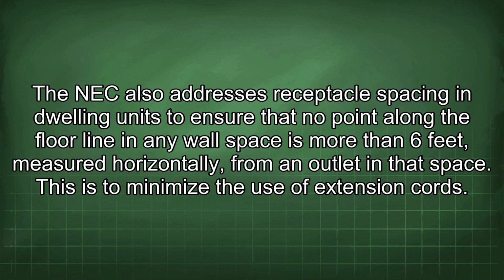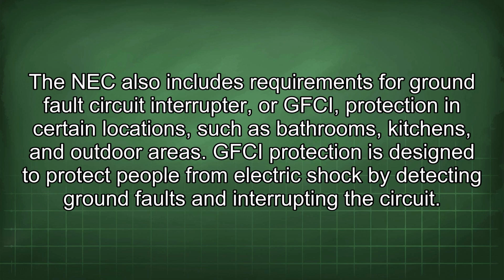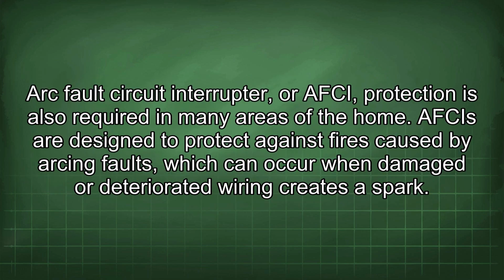The NEC also addresses receptacle spacing in dwelling units to ensure that no point along the floor line in any wall space is more than 6 feet, measured horizontally, from an outlet in that space. This is to minimize the use of extension cords. The NEC also includes requirements for ground fault circuit interrupter, or GFCI, protection in certain locations such as bathrooms, kitchens, and outdoor areas. GFCI protection is designed to protect people from electric shock by detecting ground faults and interrupting the circuit. Arc fault circuit interrupter, or AFCI, protection is also required in many areas of the home. AFCIs are designed to protect against fires caused by arcing faults, which can occur when damaged or deteriorated wiring creates a spark.